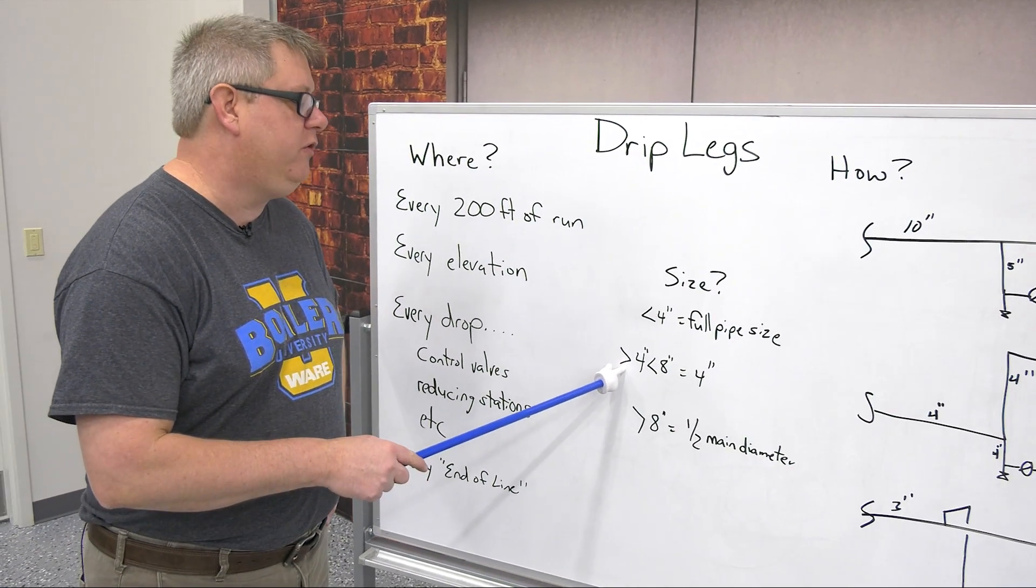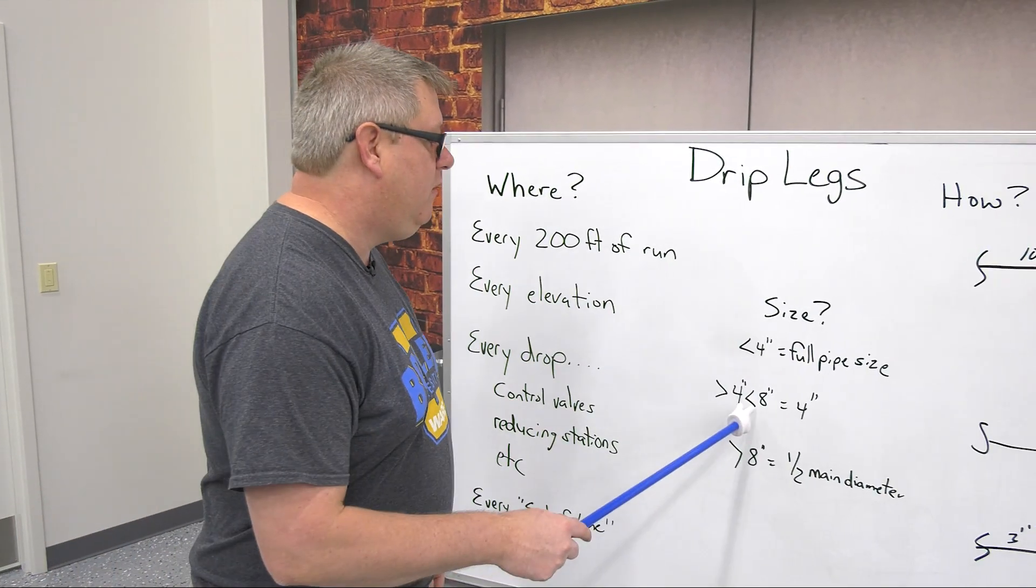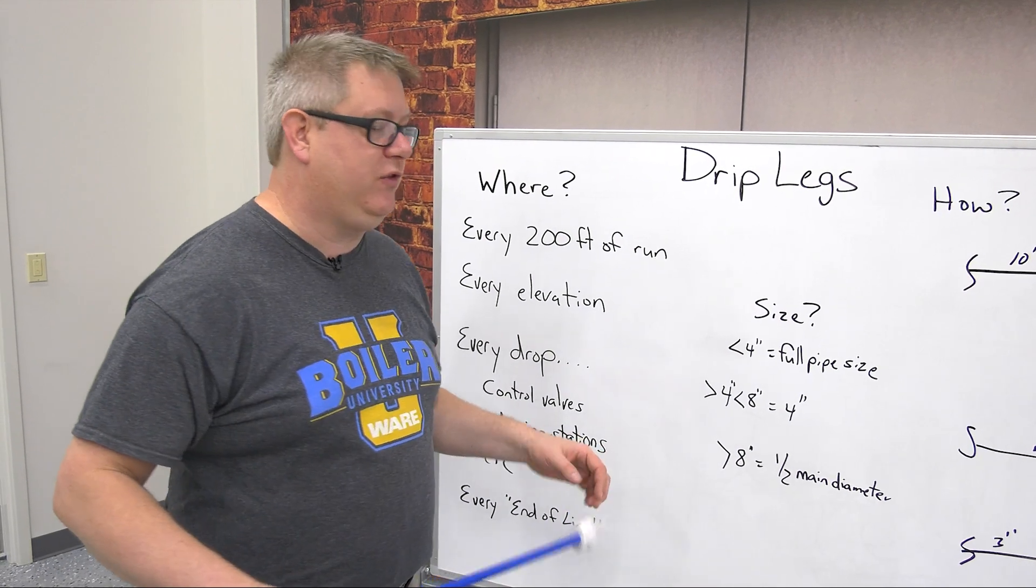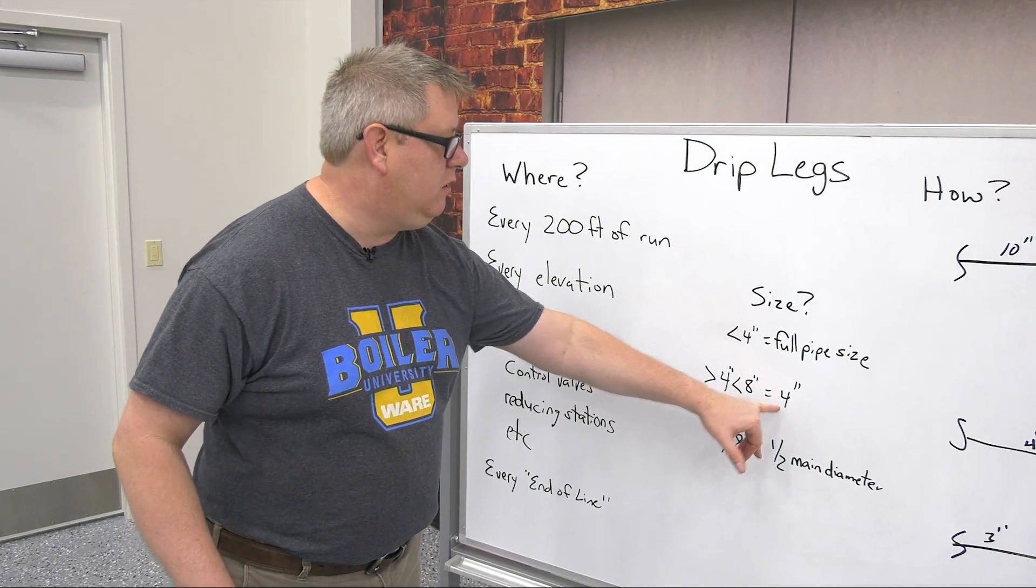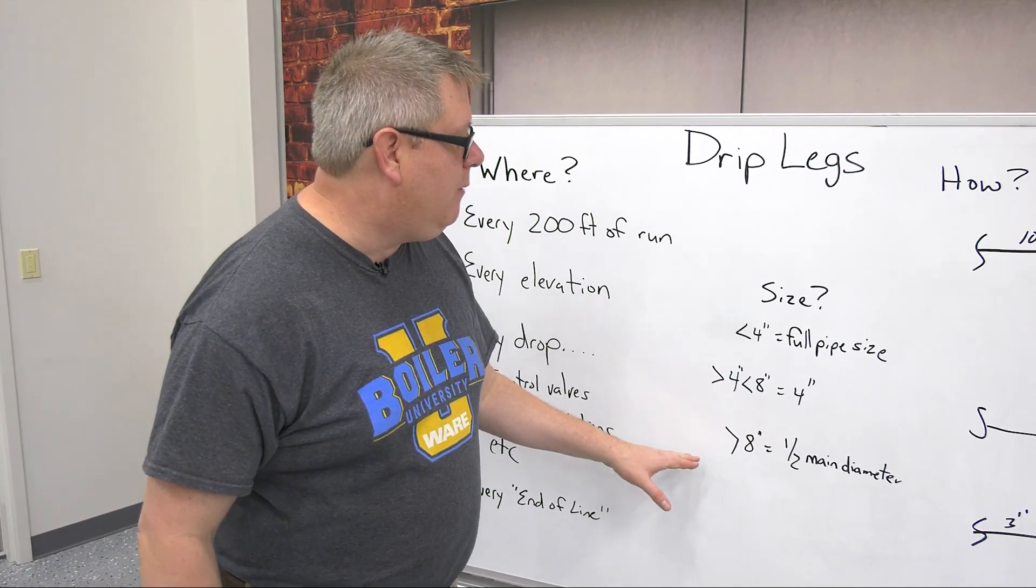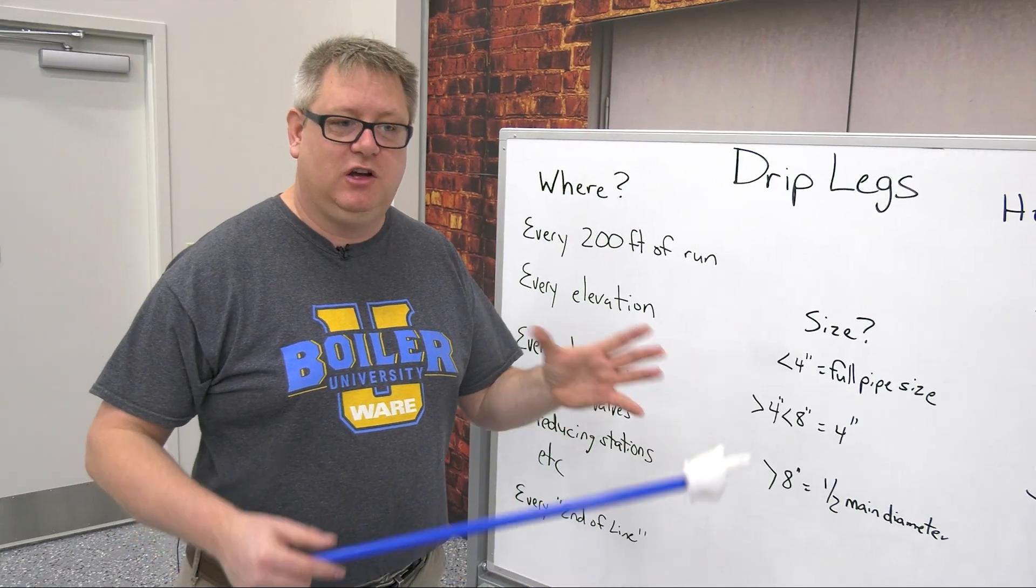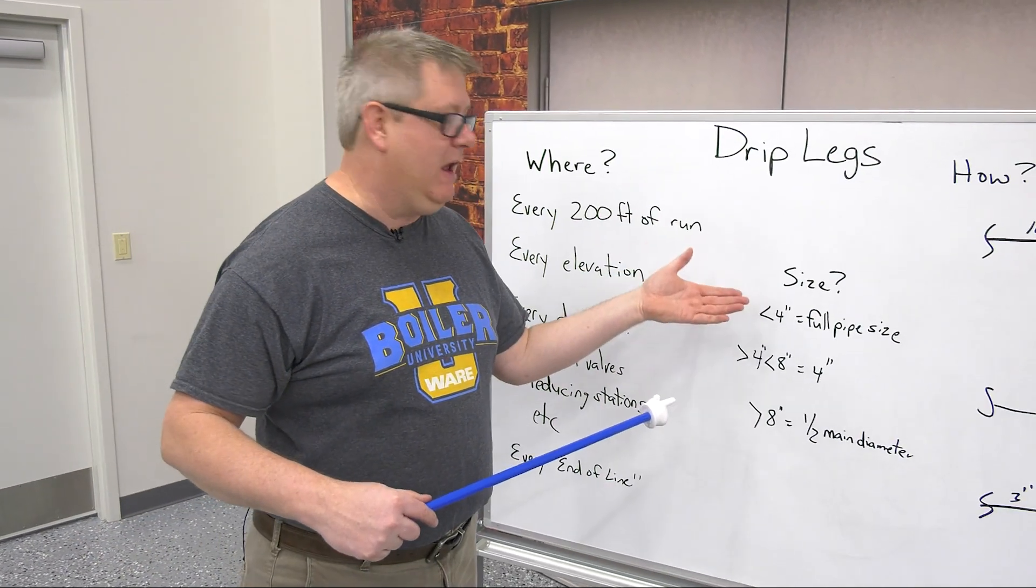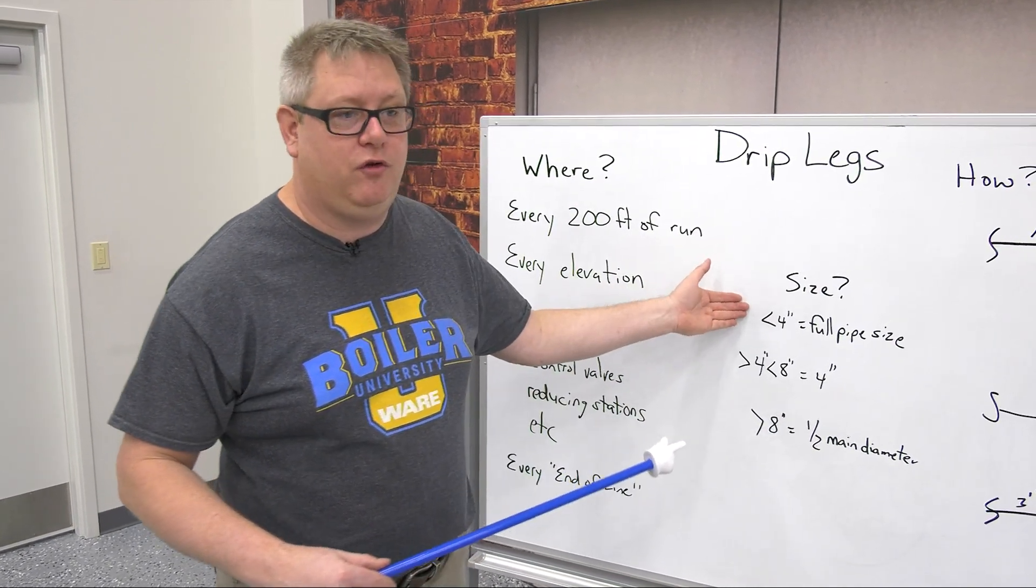If we're larger than a four inch main, we're going to use four inch for our drip leg up to eight inch pipe. So basically that's half until we get to eight inch. Above an eight inch main, we're going to use half of the main diameter. So if we have a 12 inch main, a six inch drip leg, an eight inch main, a four inch drip leg, a two inch main, a two inch drip leg.